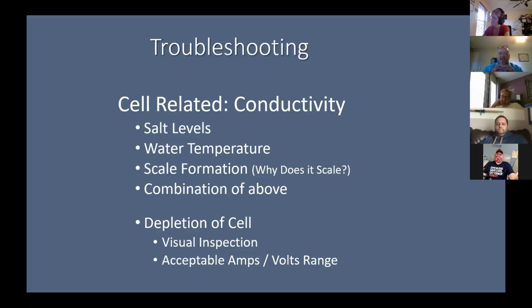But why does a cell scale up? The first one is that saturation index. Anytime you come across a cell that's scaled up, you always want to check your water chemistry and check the saturation index, okay? Typically, when your water chemistry is out of balance, you'll see the cell scale up in 2 weeks or longer. If it scales up in 2 weeks or less, the typical reason is because your power supply is not doing that self-cleaning feature as it should. Okay, so now there's a power supply issue that's not going through the reverse polarity.